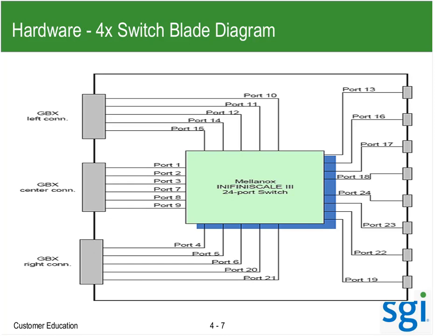The cabling between IRUs is done manually, but engineering and manufacturing do have a cable verification tool. It basically checks the integrity of the cabling. So before they take the system apart in Chippewa, they run the cable verification tool to make sure it passes. And then when it's recabled back at site, they run the cable verification tool again to make sure it's cabled the way it was when it left the factory.